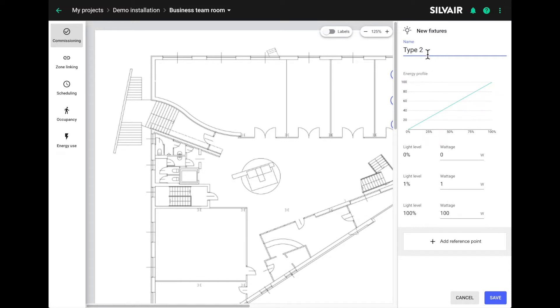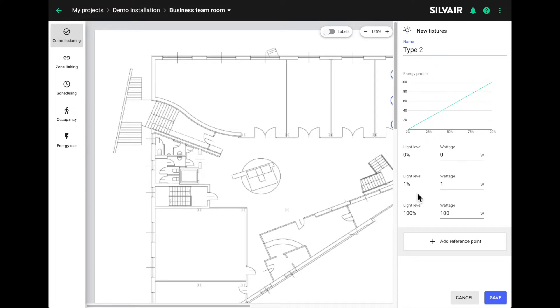Give the fixture type a name and enter the energy consumption you recorded at various output levels. We've got another video tutorial that shows you how to do this or have a look at the application note, which you can find on our website in the knowledge base. The 0%, 1% and 100% output values are mandatory, but the more points you measure, especially at each end of the scale, the more accurate the results.